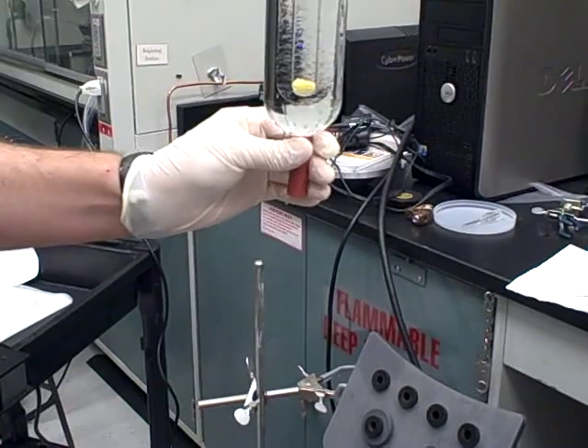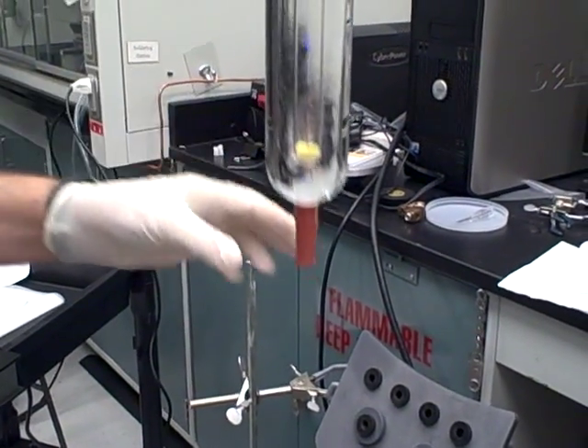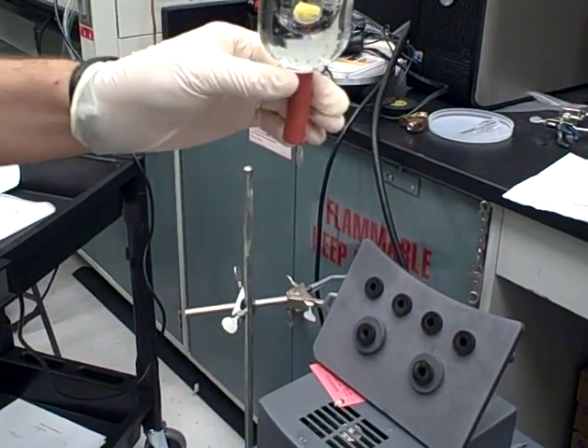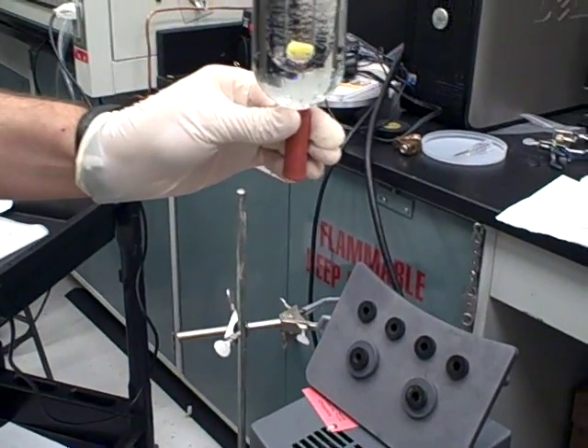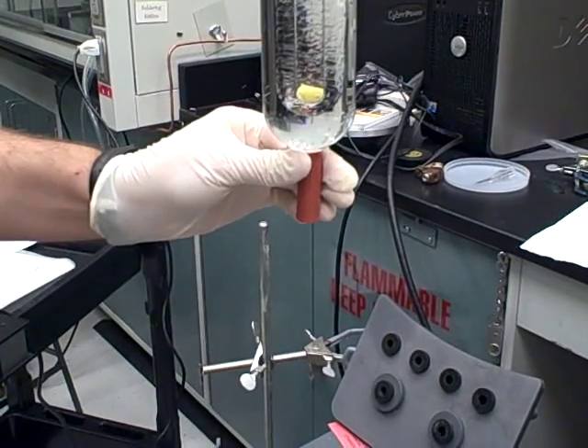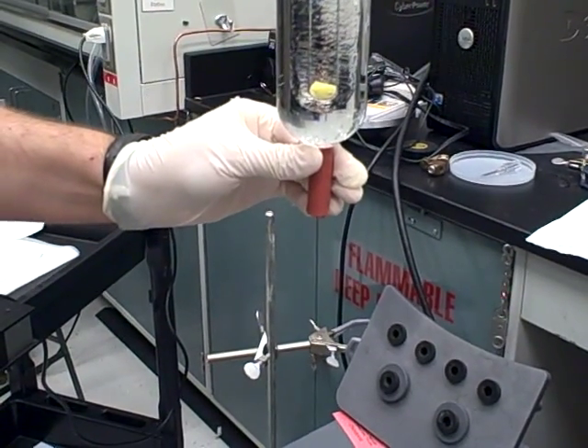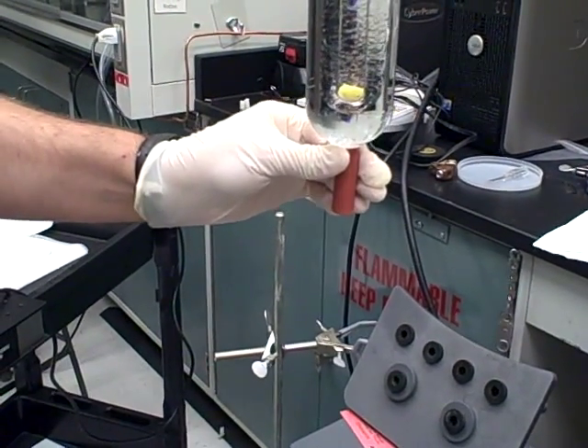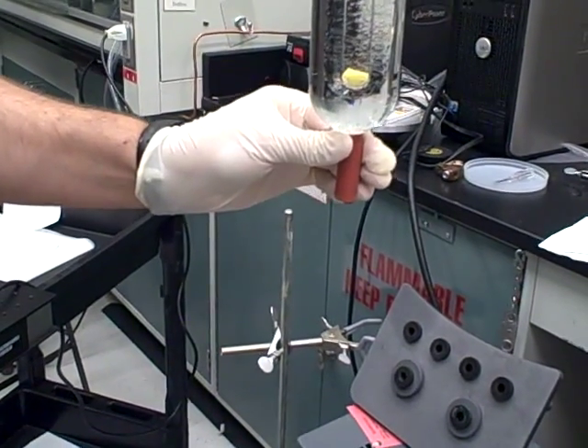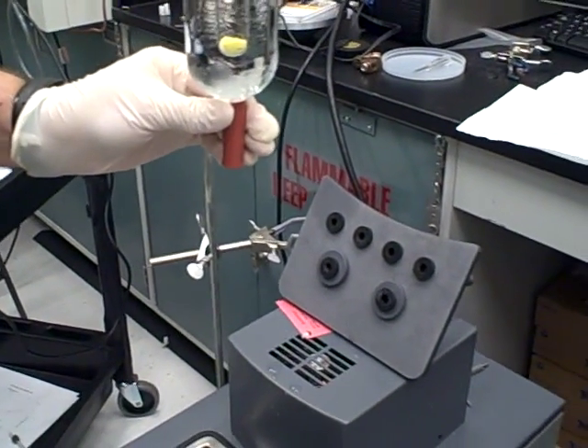So at the very bottom, you can see the bottom of this tube is where that yellow sponge is. That is going to be where my calibration point is, and that is defined at the triple point of water to be 0.01 degrees C. And that's where this has to touch the yellow?